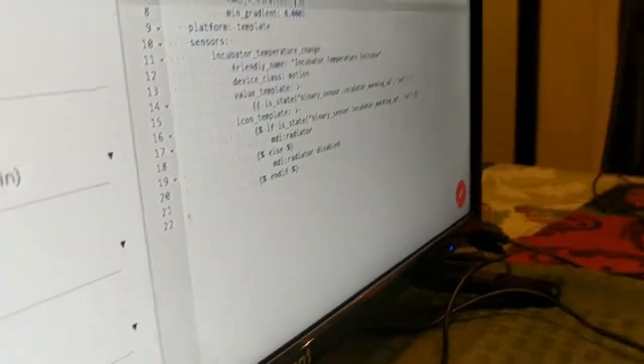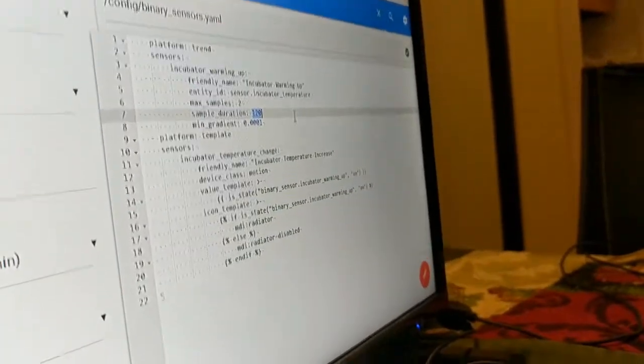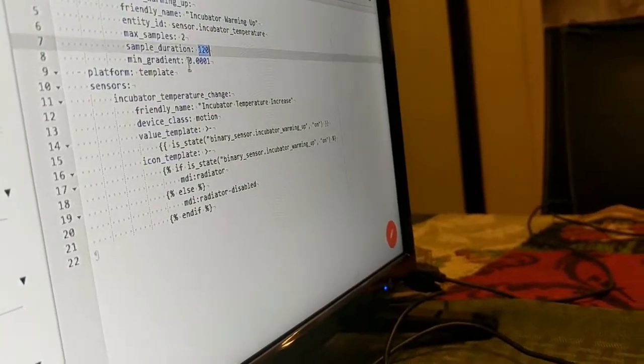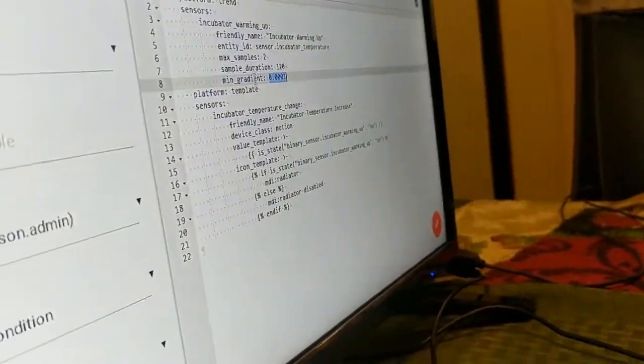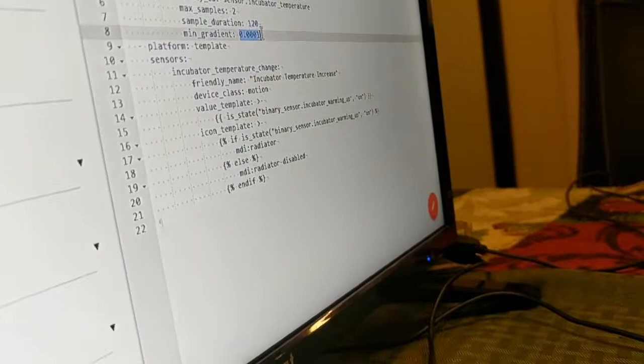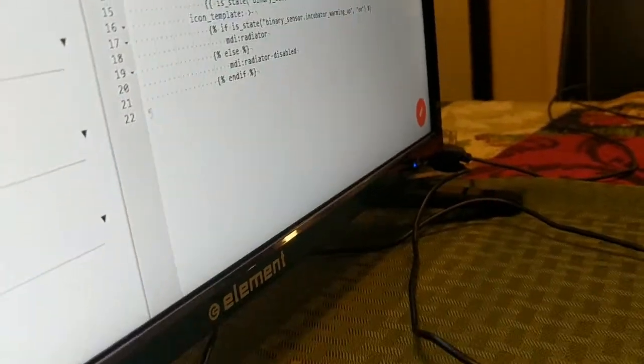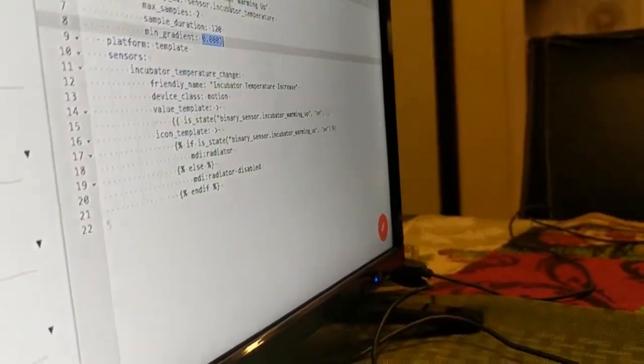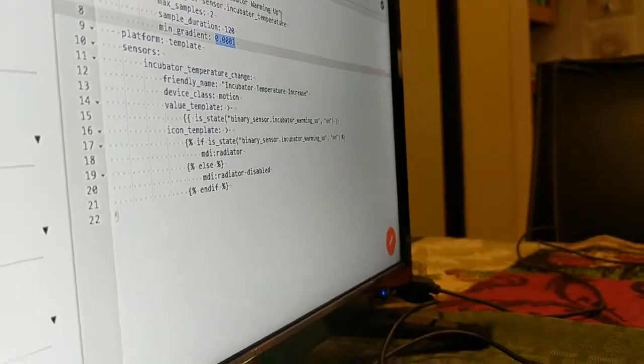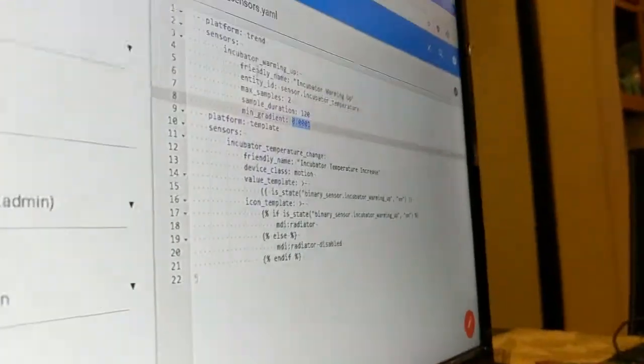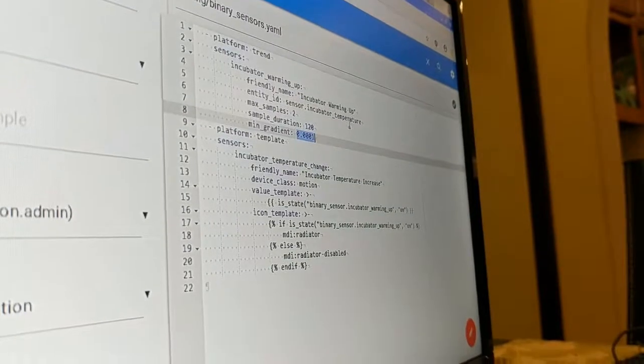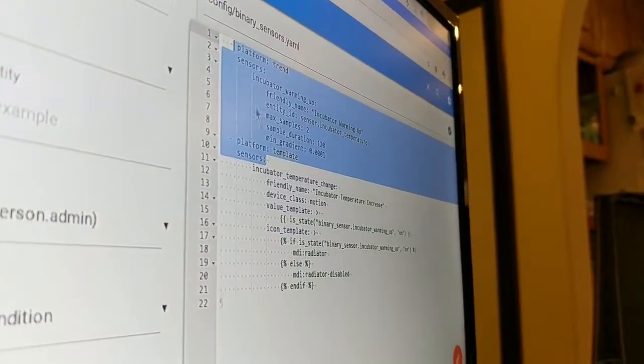then we care about a duration of 2 minutes, 120 seconds, and it's going up even a tiny little bit - that's the minimum gradient, saying we're going up just a little. If it's going up just a little between two samples within 2 minutes, we'll say the incubator is warming up. We don't have to create one for cooling down, because if it's not warming up, we'll assume it's cooling down. So we just create this one for warming up.